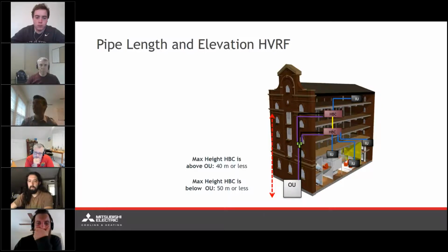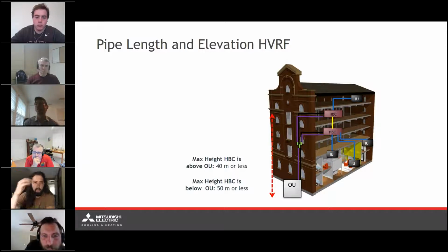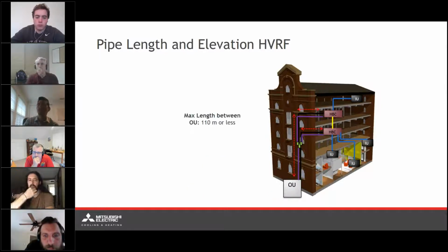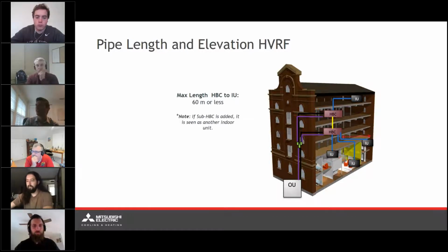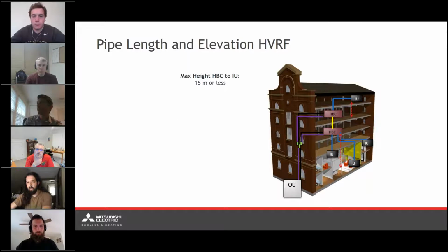So one of the pipe limits that we have to look at is that, for this instance where the condensing unit is on the ground, we can have the HBC be 40 meters or less, so just about 130 feet or so, away from the condensing unit. We also have total line length of 110 meters from the condensing unit. From your BC controller to your furthest fan coil, we're going to be looking at 60 meters or less. The height difference between HBC and your fan coils can be 15 meters or less. Between fan coils, 15 meters.